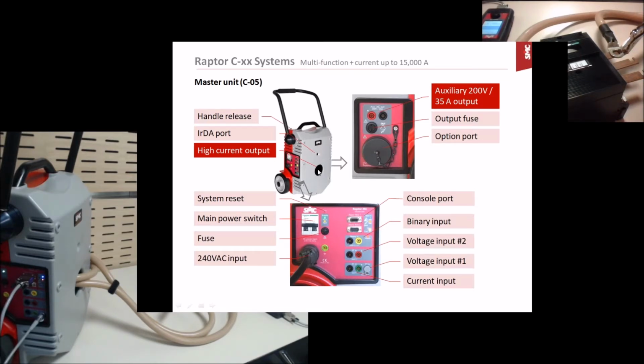We use the induction method to produce high current, so you save some connections. You don't need to connect cables to the unit. Just insert the cable inside the unit and come from the other side to both sides to the machine that you are testing. Okay, there is also an auxiliary output for low current but higher voltage. Okay, up to 200 volts here.